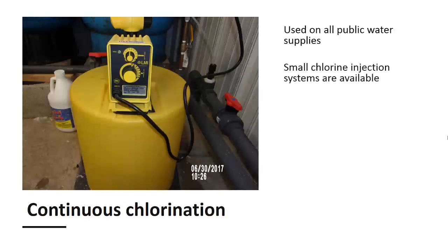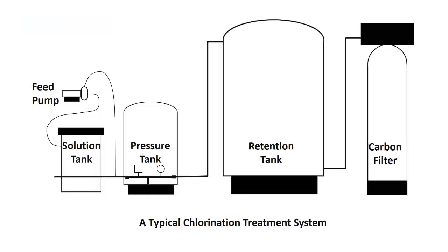Another type of disinfection used in all public water supplies in the United States is continuous chlorination. On household wells and springs, small chlorine injection systems are available. The feed pump injects chlorine from a solution tank before the pressure tank. A larger retention tank is also installed to make sure that the chlorine has plenty of time to kill bacteria before the water moves into the household plumbing. If the resulting chlorine concentration is offensive, a carbon filter can be installed after the retention tank to remove the chlorine after it has done its job.